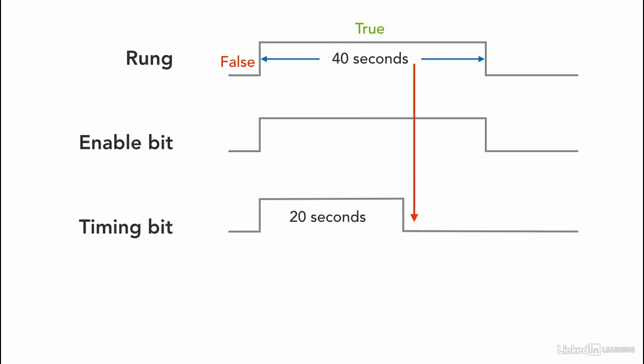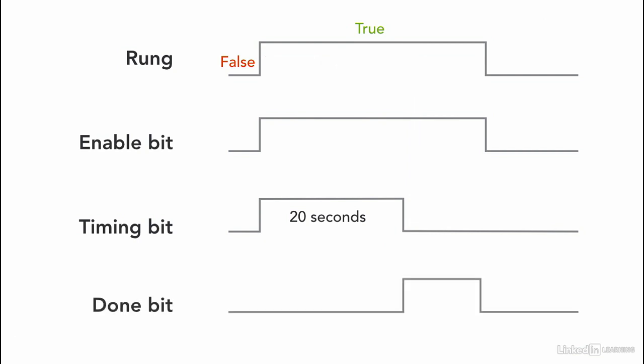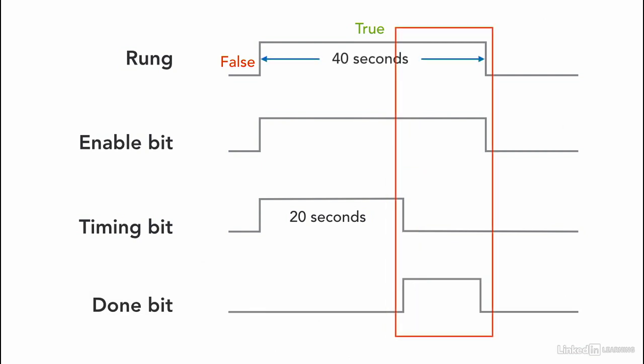Even if the rung is true, the timer timing bit goes to false after reaching the preset value. The done bit is activated after the timer is done and stays on as long as the rung is true. Once the rung goes to false, the timer done bit resets too.